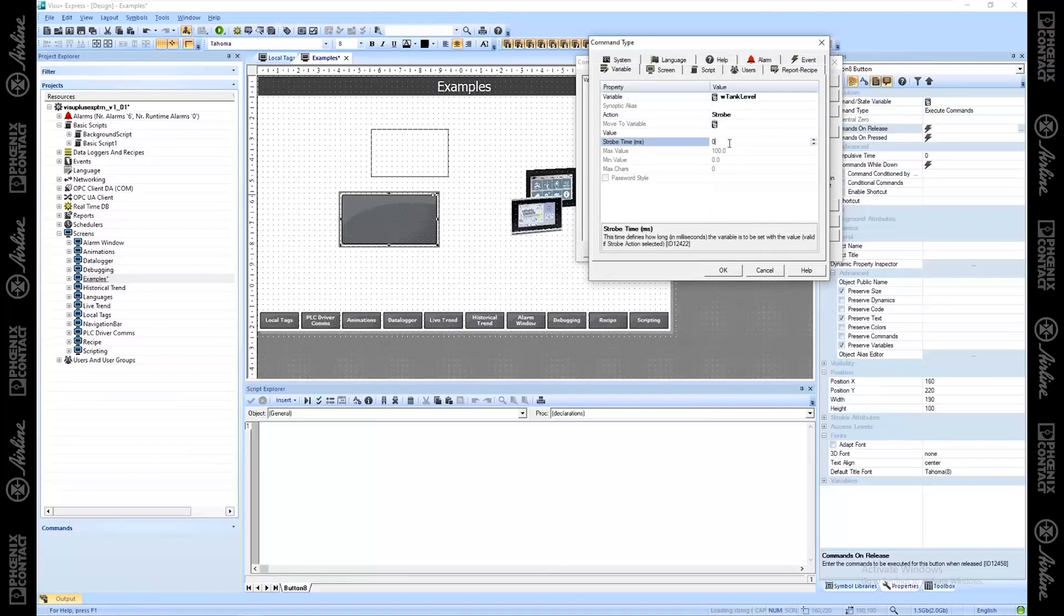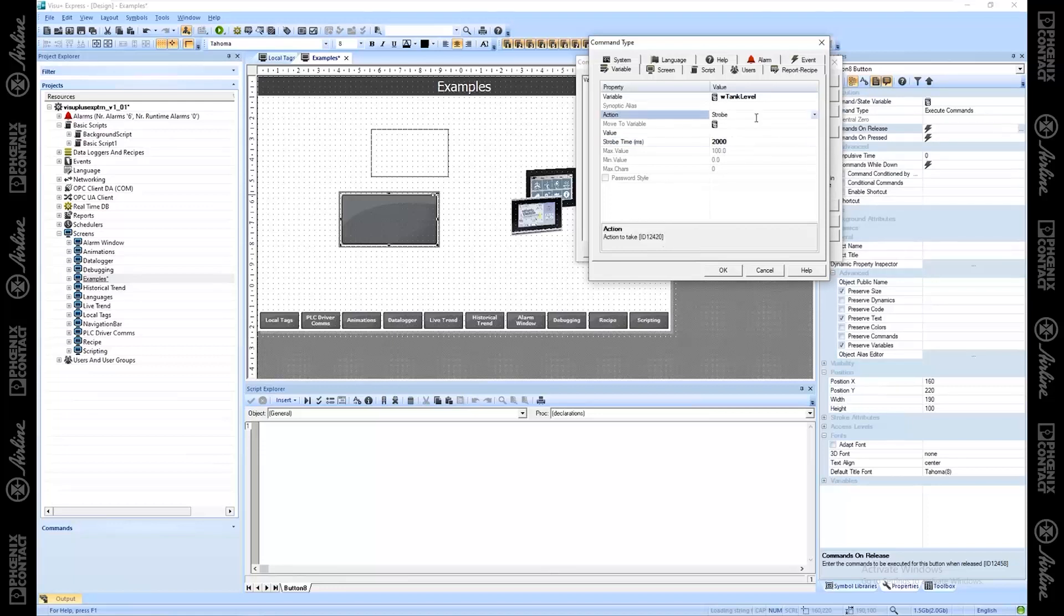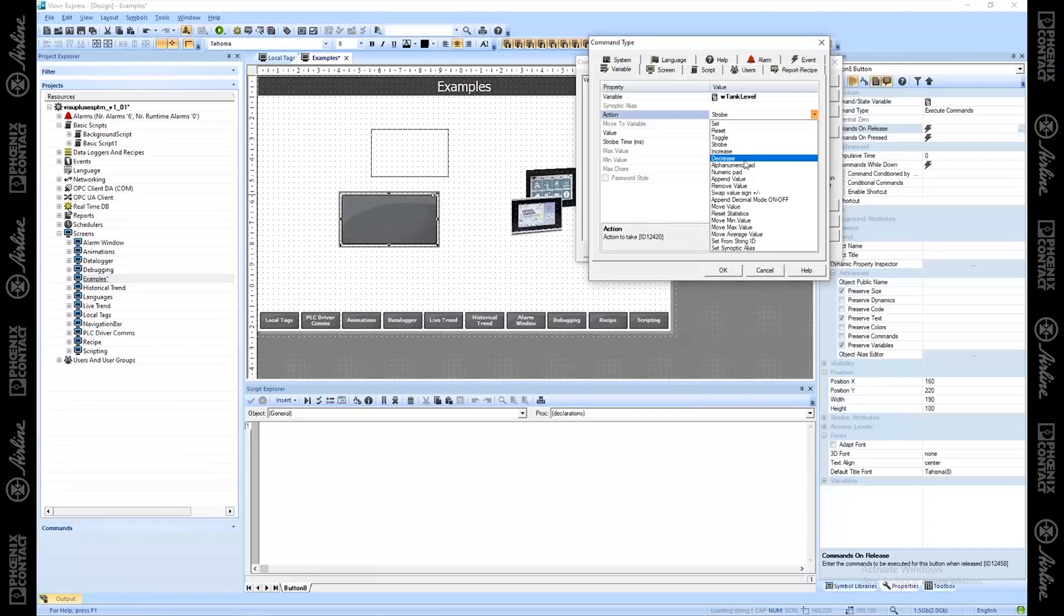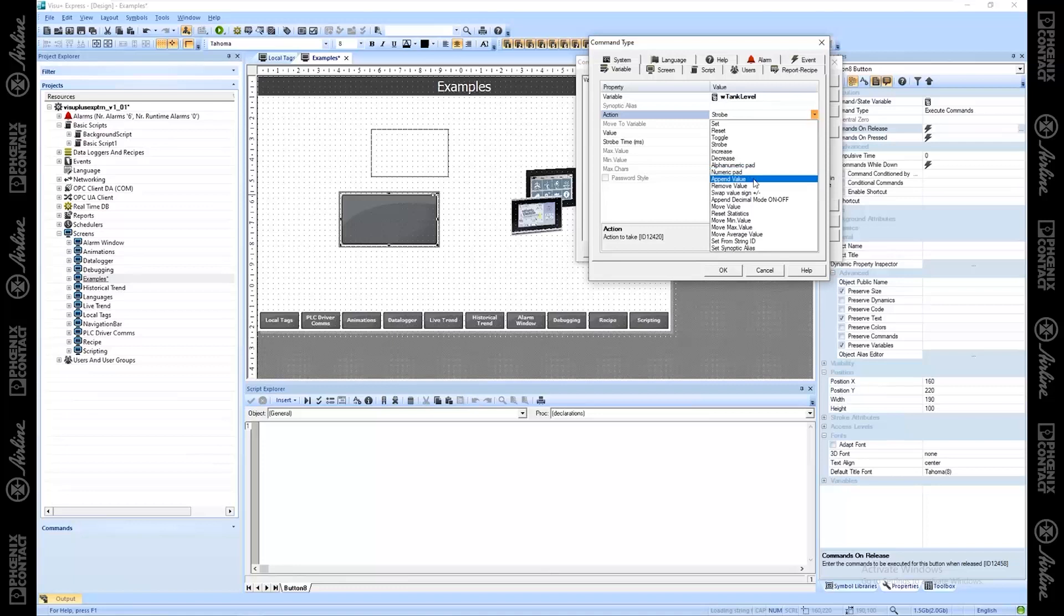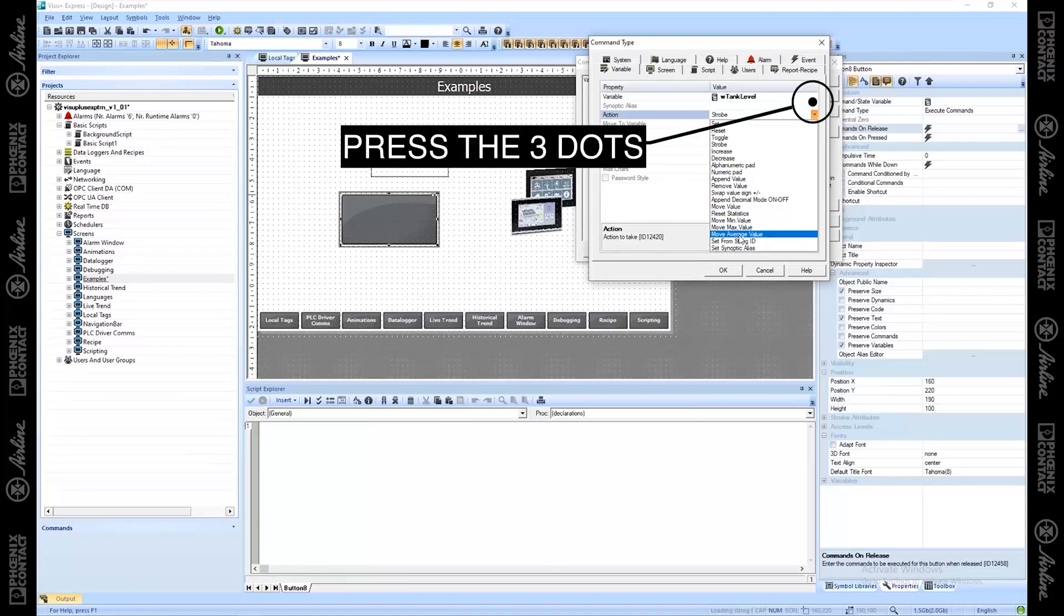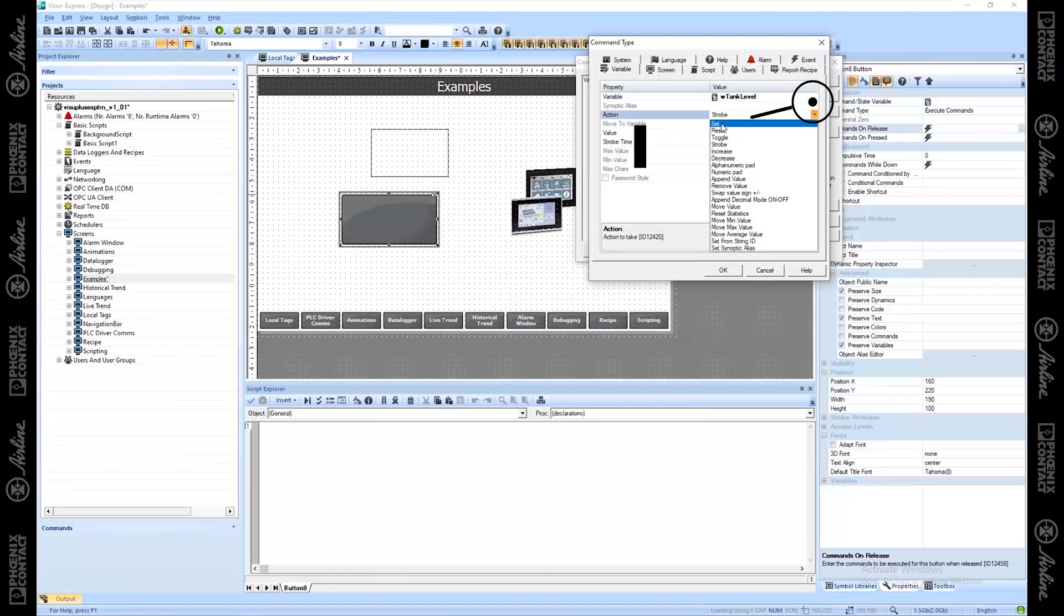Strobe means hold it for x amount of time. If I hit strobe, you see this strobe milliseconds is now available. So if I put 2000 here, I'm going to hold this value for 2000 milliseconds. This is usually useful for a Boolean value. If I wanted to toggle a bit and have it held after I've released for two seconds, use the strobe feature. Increase or decrease, swap the signs, make a positive or negative. The most common ones are going to be set, reset, toggle, strobe.